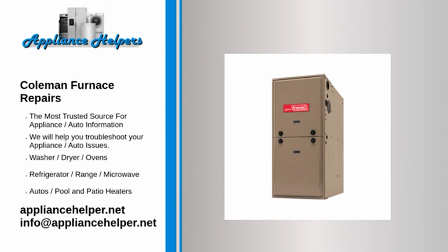Coleman furnace blower not running. The blower motor blows air through the return vent, past the heat exchanger, and into the home's venting. First, make sure that power is getting to the motor. If power is getting to the blower motor, but the motor does not run, the motor may be burned out. If the blower motor is burned out, replace it. If the blower motor hums, check the blower fan to ensure that it spins freely. If the blower fan is unobstructed but does not spin freely, replace the blower motor.